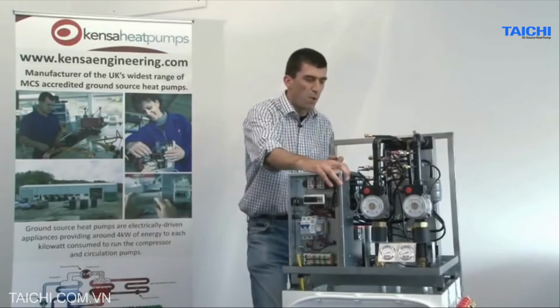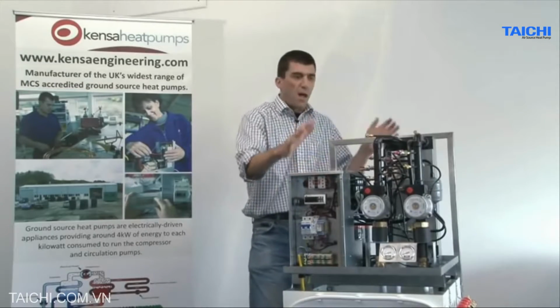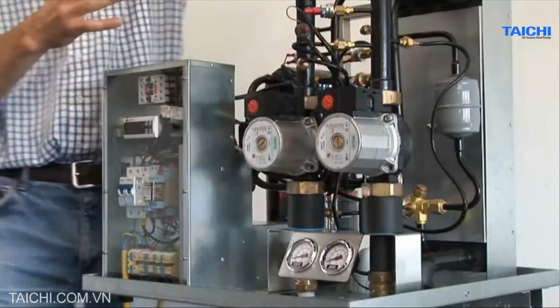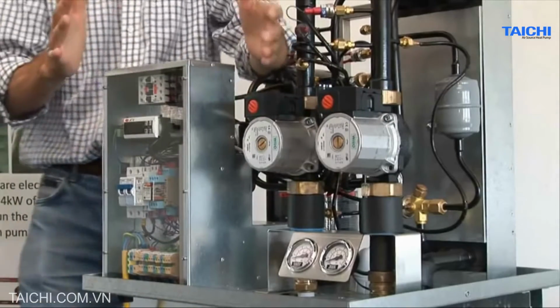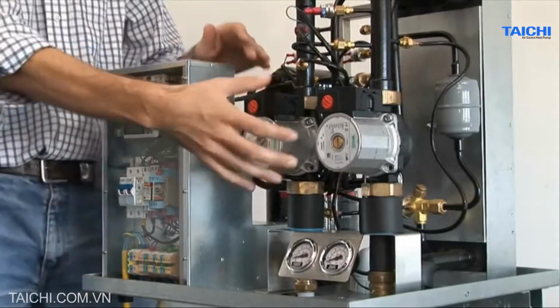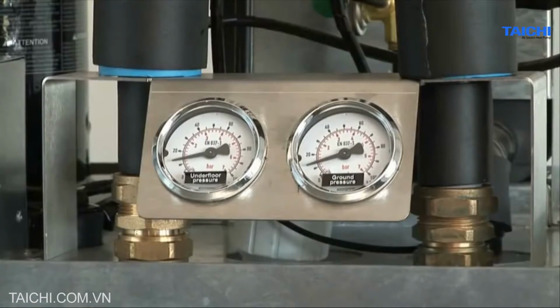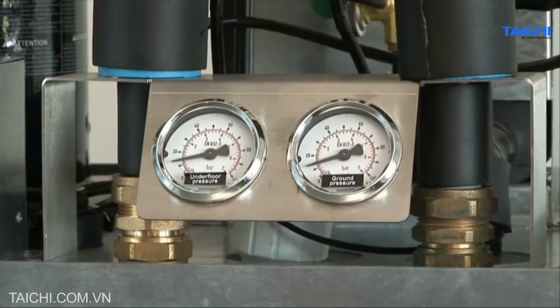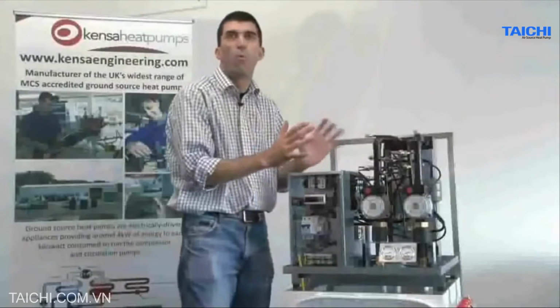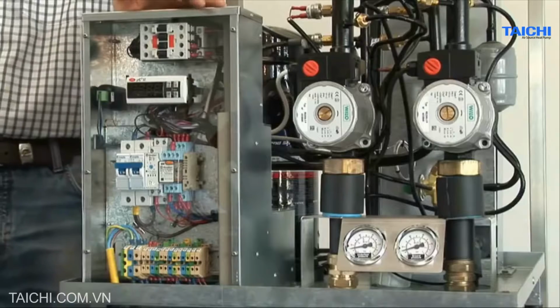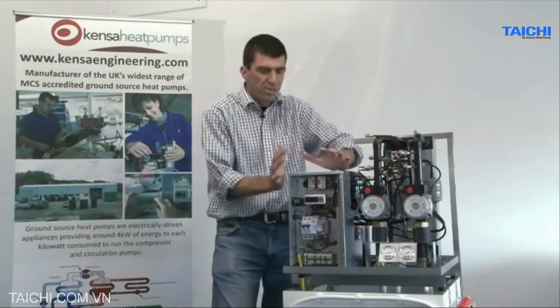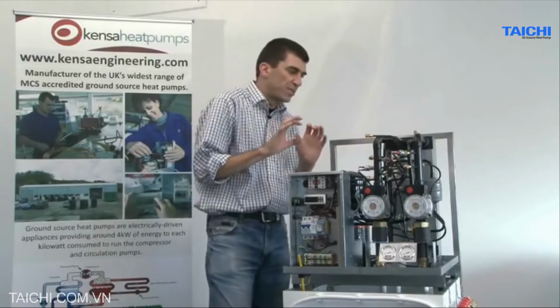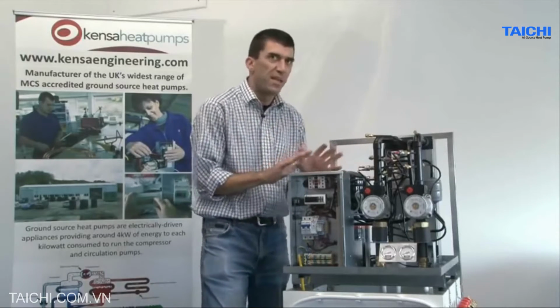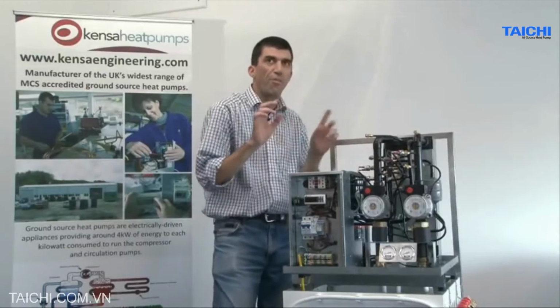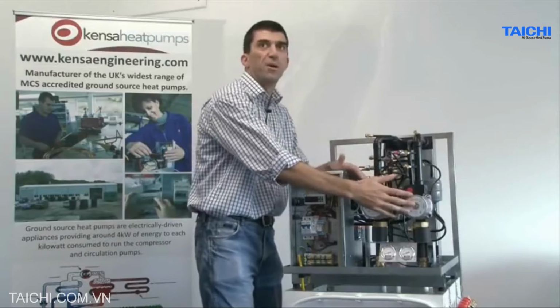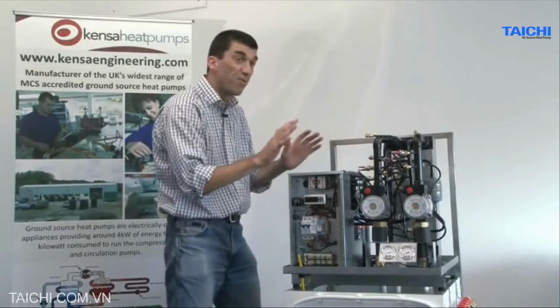So what's actually in the box? There's a number of key components. I'm going to just talk you through. We've got 2 water pumps. A load side water pump, which is your hot side, your hot water that's going to distribute around your house, and a ground side water pump, which is pumping the water around your ground arrays. I say water, in actual fact it's a mixture usually of ethylene glycol and water. It gives it some freeze protection. We've got an electrics box. Yeah, it looks complex. Most of its functionality is safety and temperature control. Really all it does in terms of operation is turn on and off 3 electric motors. 2 of those electric motors are in the water pumps. Let's forget about them. It's really not that important.